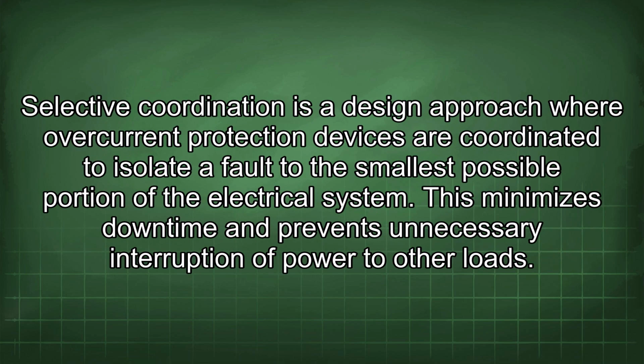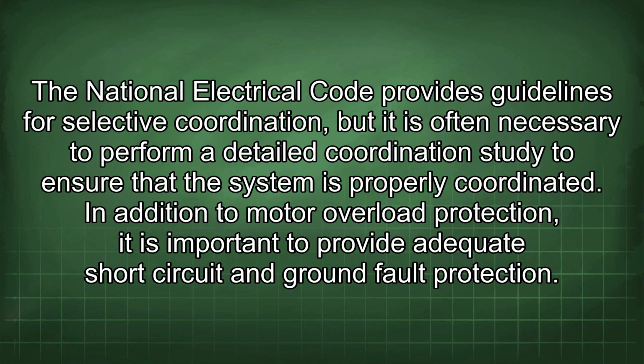Selective coordination is a design approach where overcurrent protection devices are coordinated to isolate a fault to the smallest possible portion of the electrical system. This minimizes downtime and prevents unnecessary interruption of power to other loads. The National Electrical Code provides guidelines for selective coordination, but it is often necessary to perform a detailed coordination study to ensure that the system is properly coordinated.